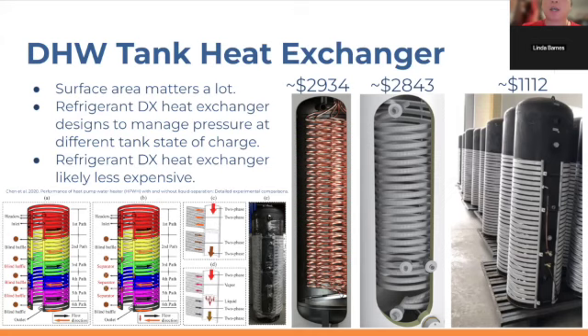In the past, there was a problem with getting enough heat to go into the tank. The heat exchanger wasn't good enough to transfer enough heat through the outer tank shell into the water inside the tank to actually get good domestic hot water heating performance. But that's changed in recent times through many different researchers' work on this issue.